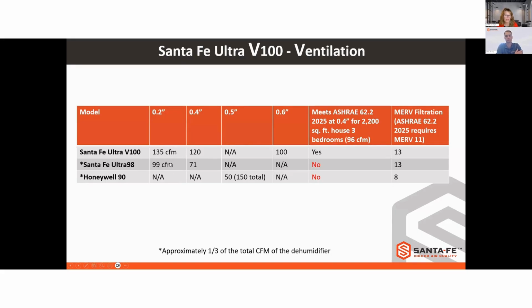So putting into the diagram here, we can get 135 no problem out of that Ultra V at 0.2. And then at 0.2, we were about 99. Now, the Honeywell unit is only going to give us the amount of CFM at 0.5, but at the 0.4, which is pretty common in a lot of HVAC systems, we have no problem meeting this ASHRAE 62 requirement of 96 CFM at that 0.4. Obviously not a problem at 0.2, and actually all the way up to 0.6, we would be able to meet this ventilation requirement with the new Ultra V100.